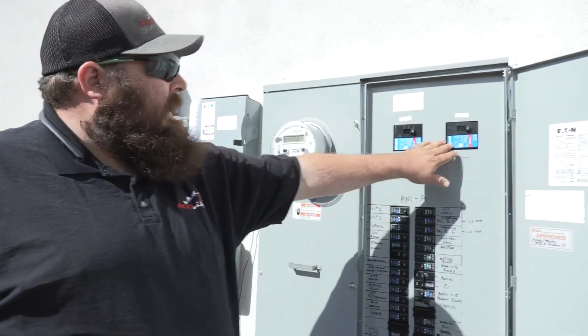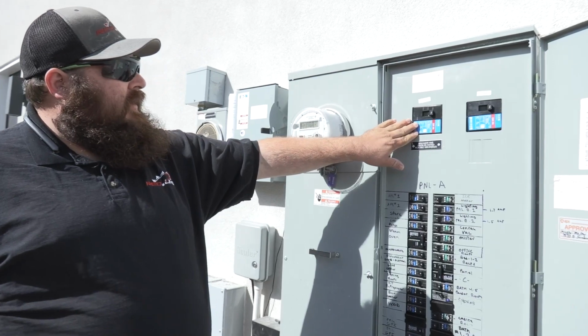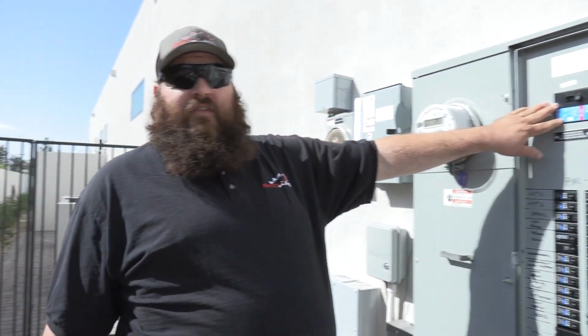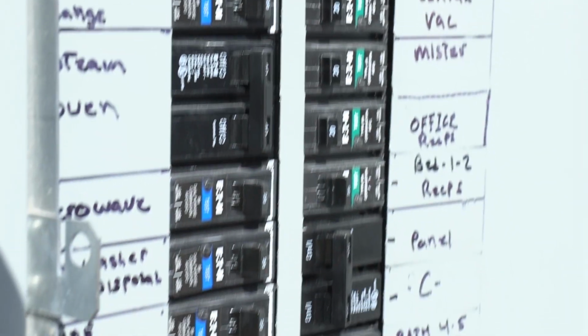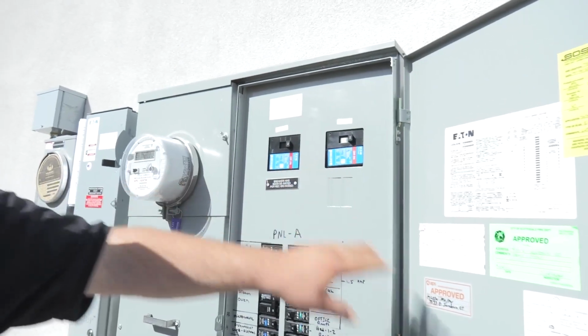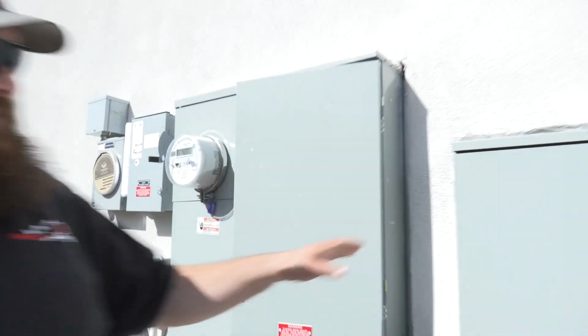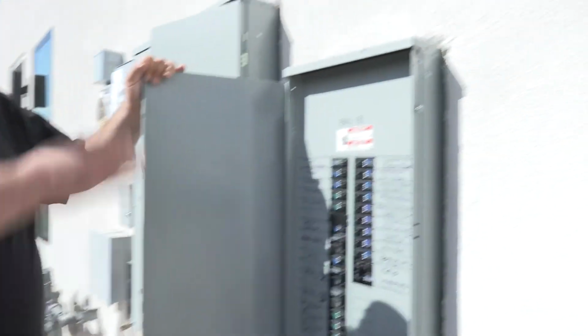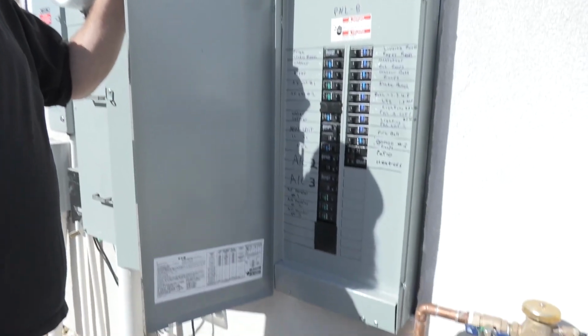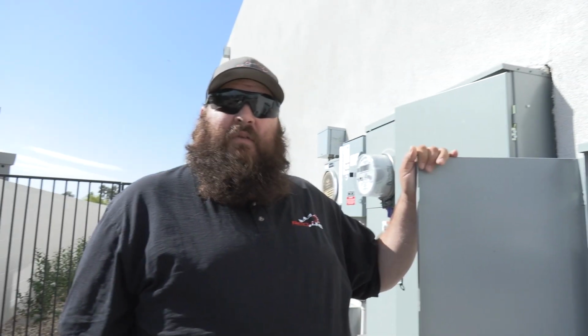You have your two different panels. We got our main breaker here, which is derated for the size of our solar system, and that feeds the breakers in this panel. Then we have another 200 amp main breaker that's going to feed a sub panel, which in this case is right next to it. The second breaker feeds all these guys. This is a large house, so that's why we have two different panels and so much power here.